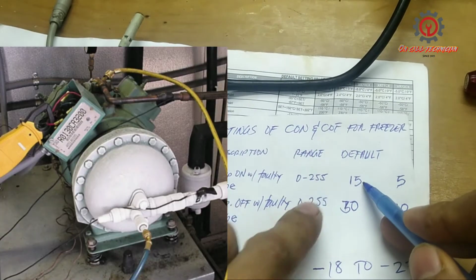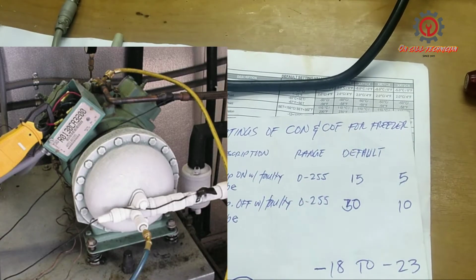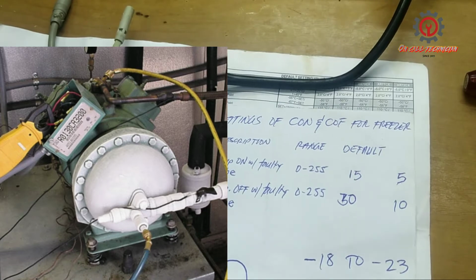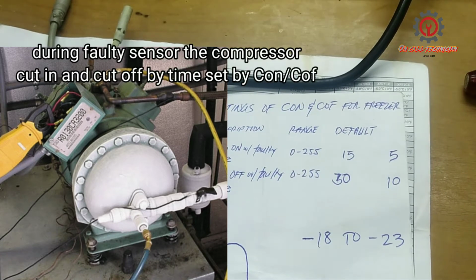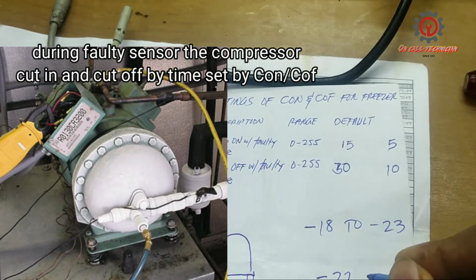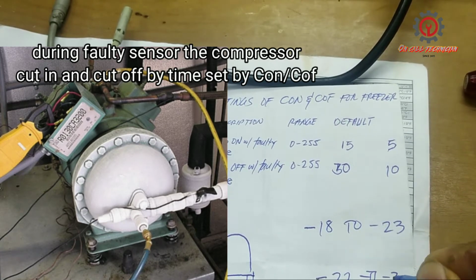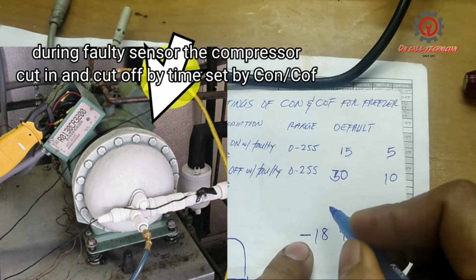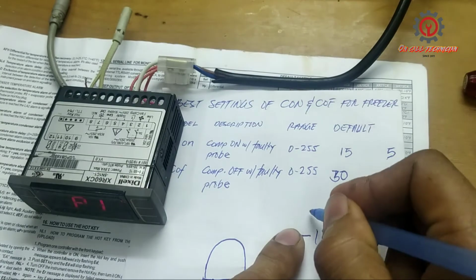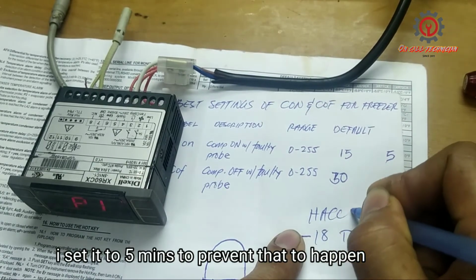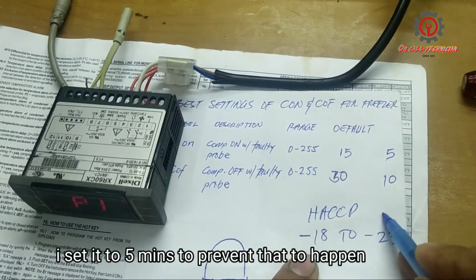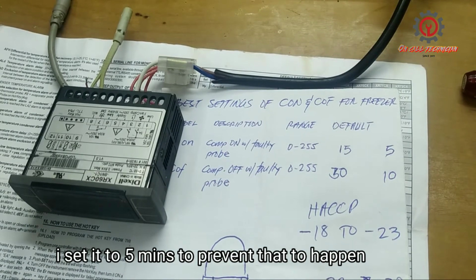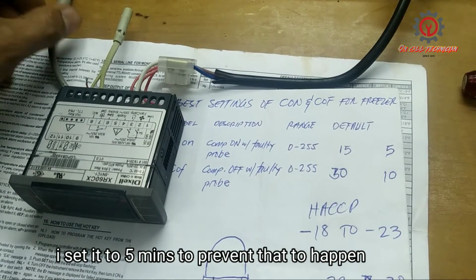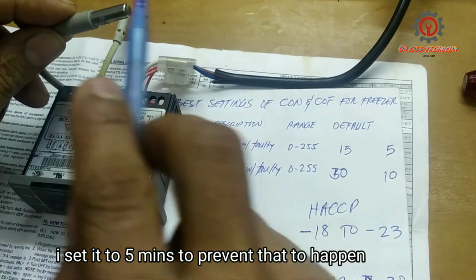That 15 minutes, this compressor keeps on running. This negative 22 for 15 minutes goes to negative 30, and this is over the standard temperature, the HACCP standard temperature. It goes to negative 30 because this sensor got a problem.